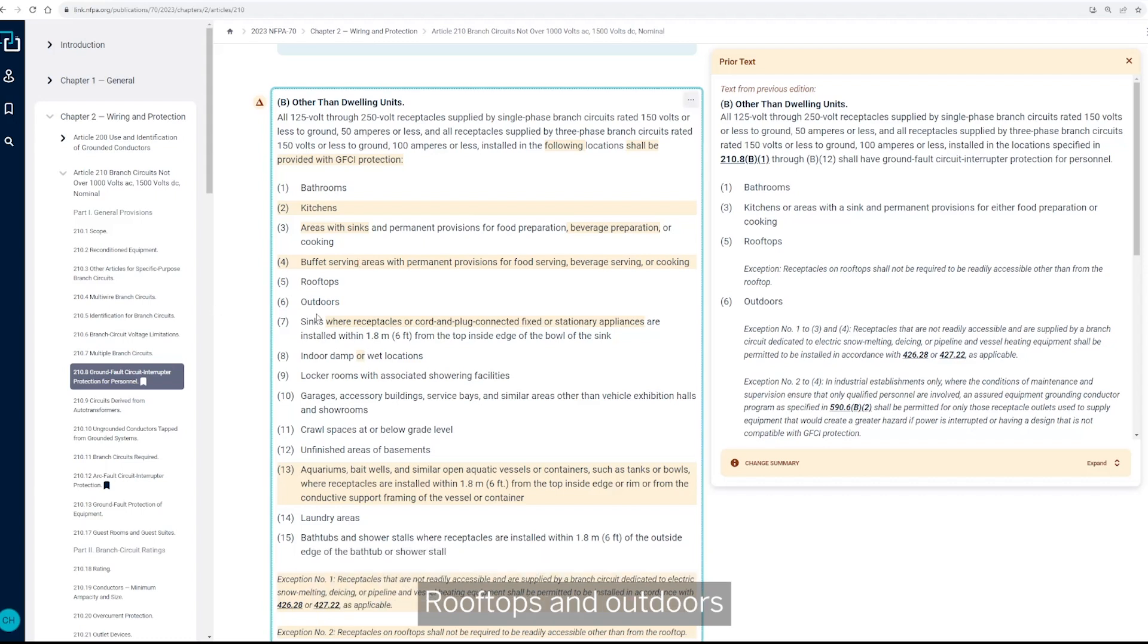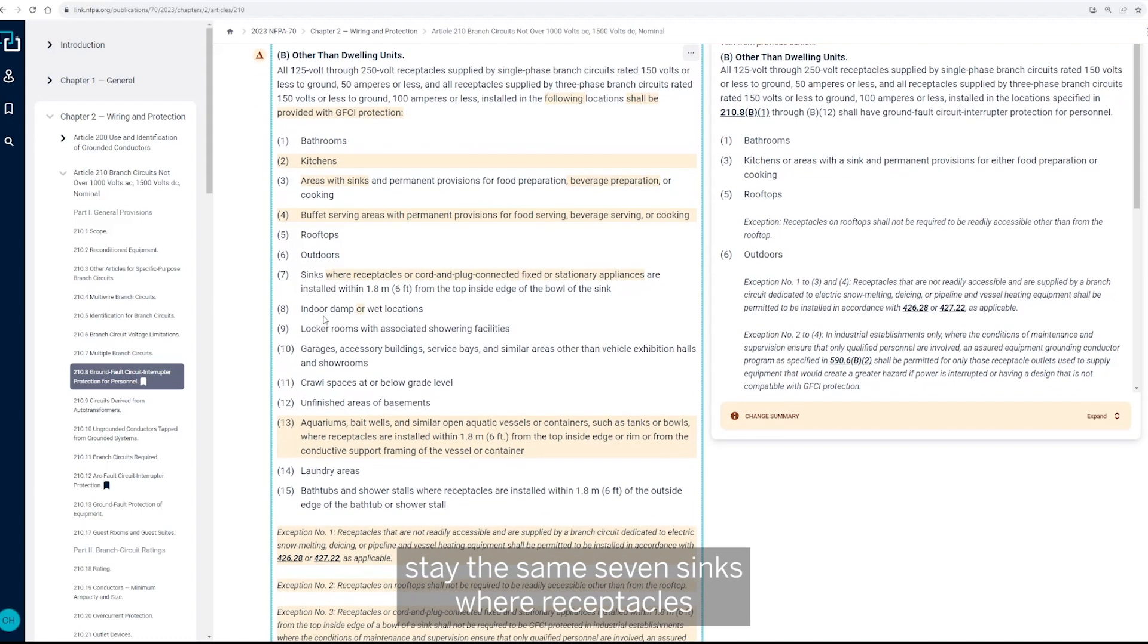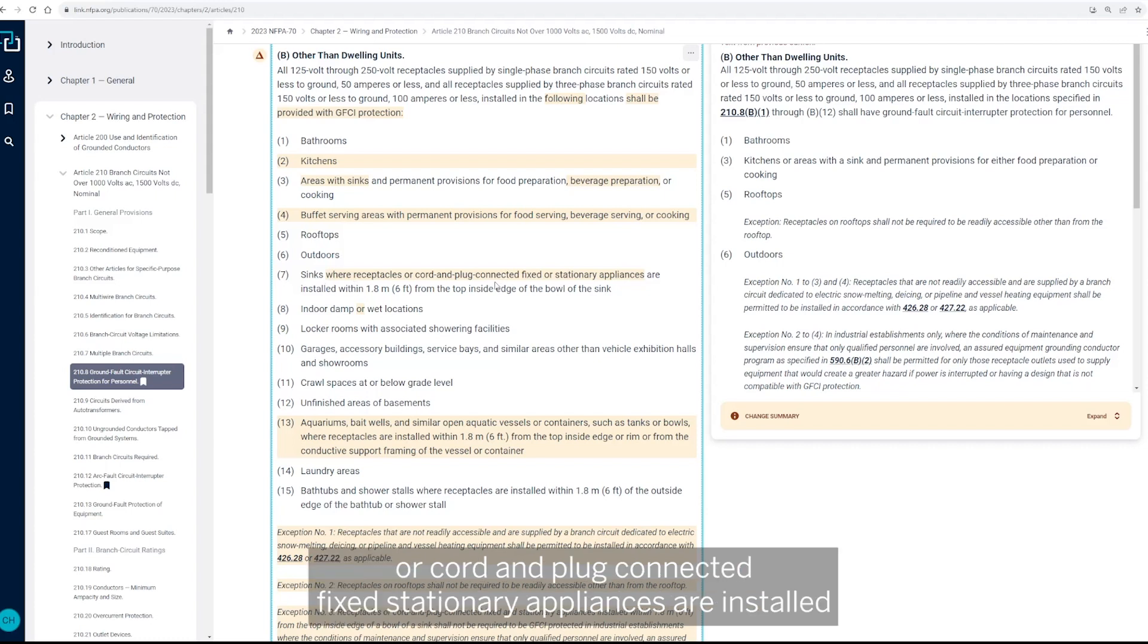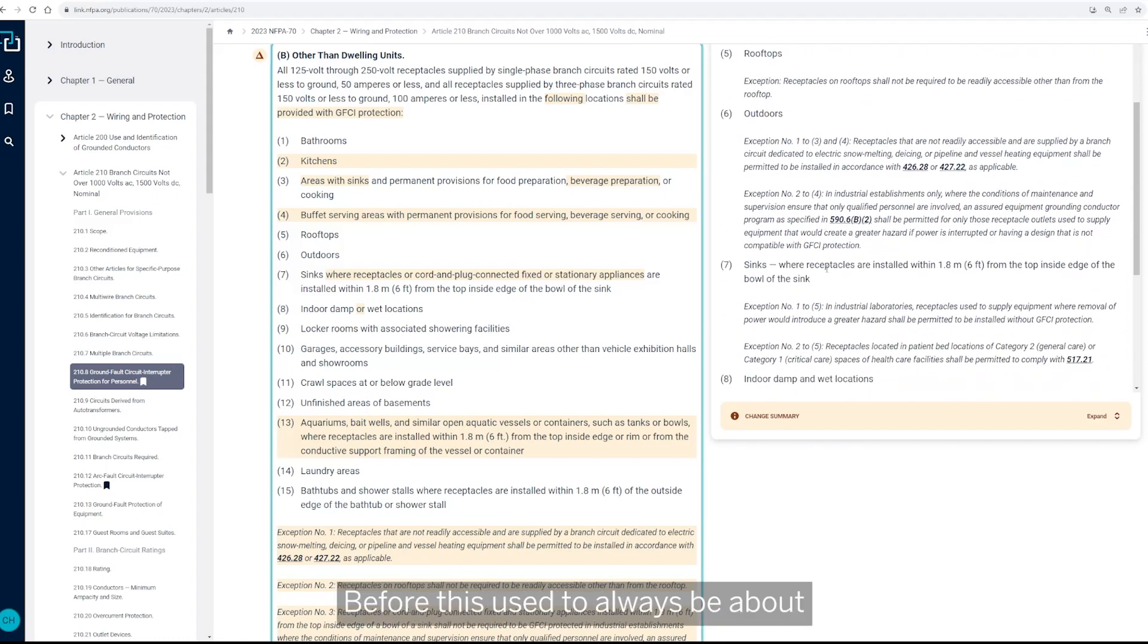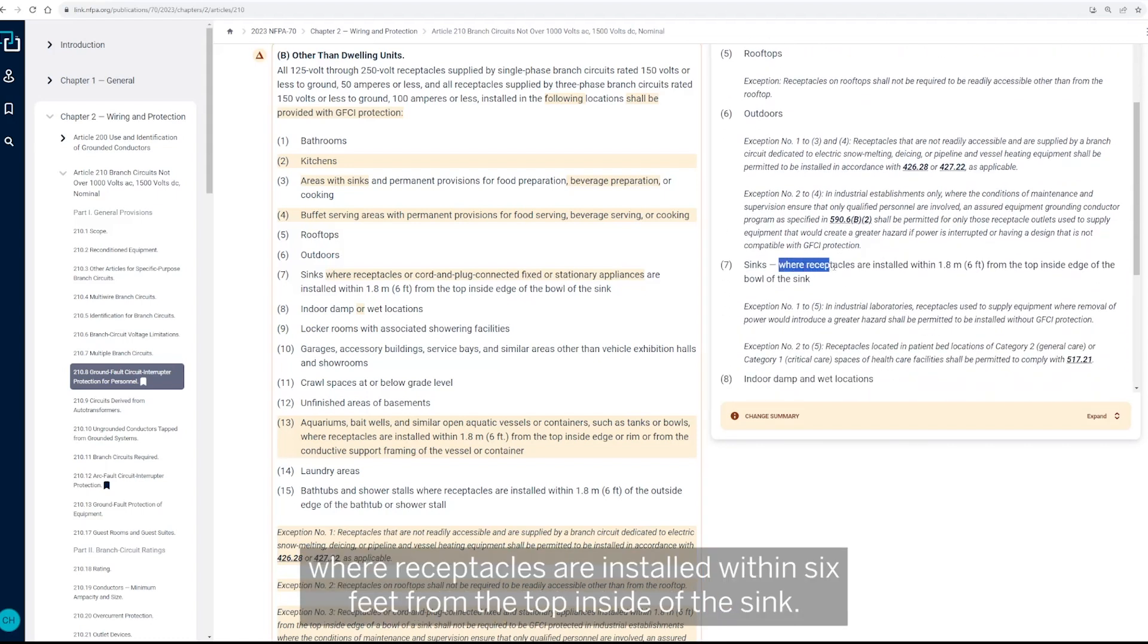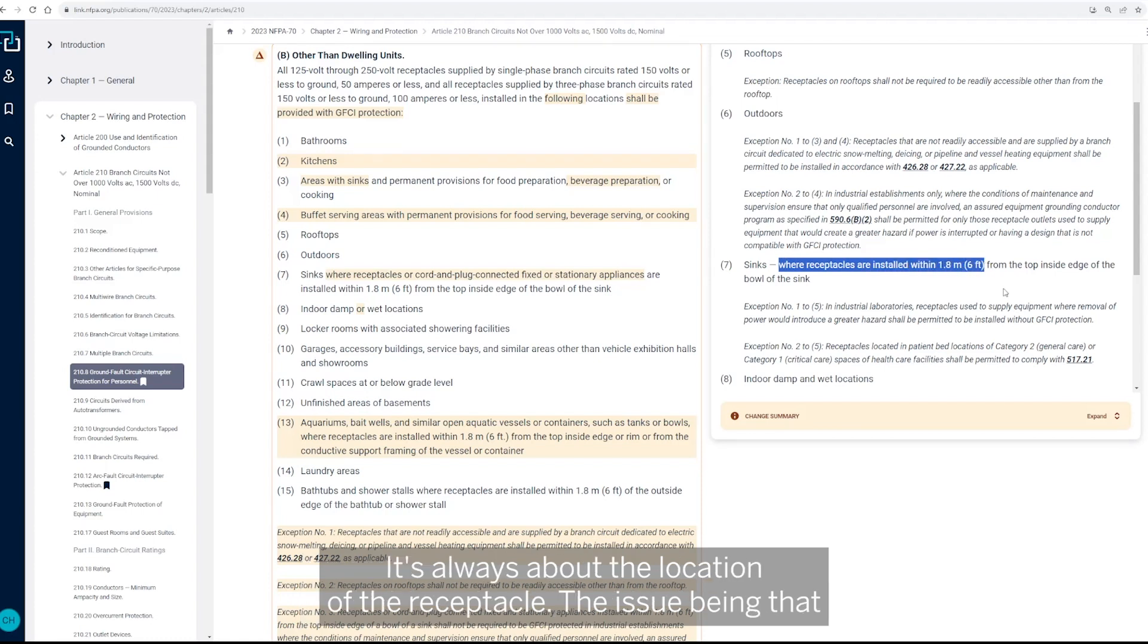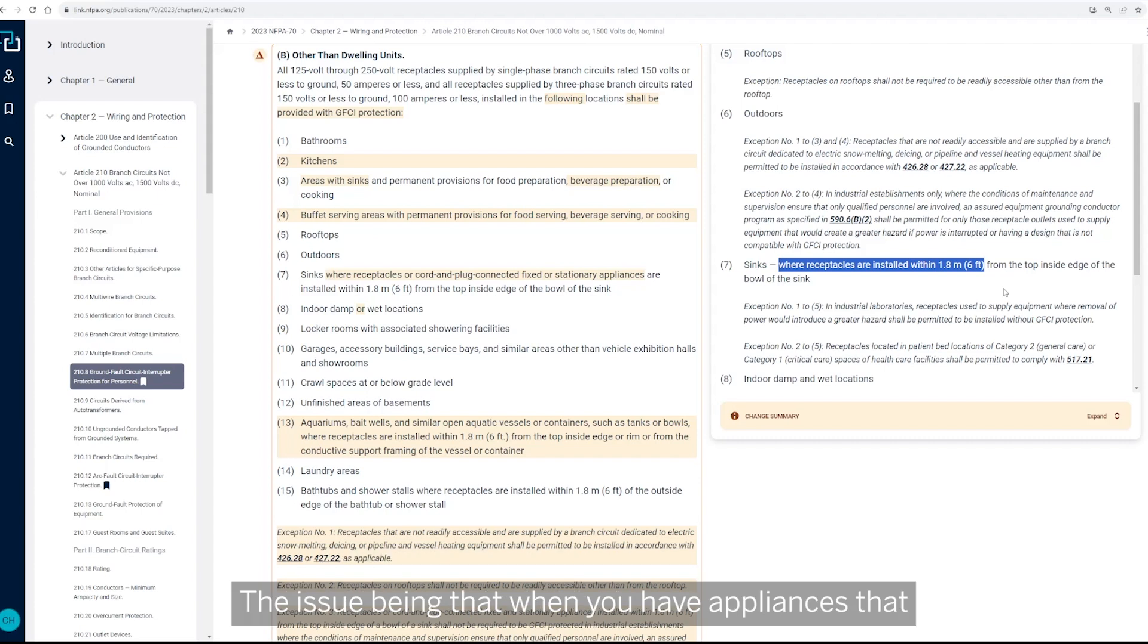Rooftops and outdoors stay the same. Seven, sinks where receptacles or cord and plug connected fixed stationary appliances are installed within six feet. So before this used to always be about, if we went over here, where receptacles are installed within six feet from the top inside of the sink. So it was always about the location of the receptacle.